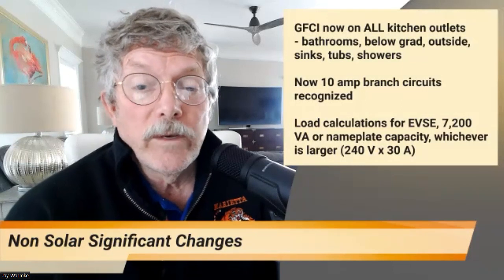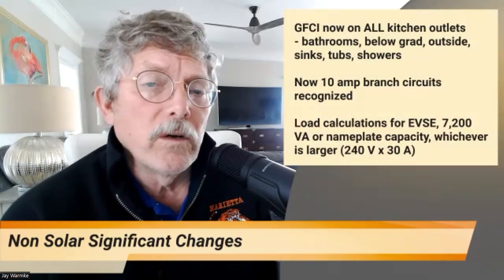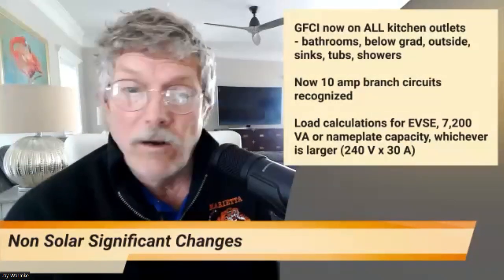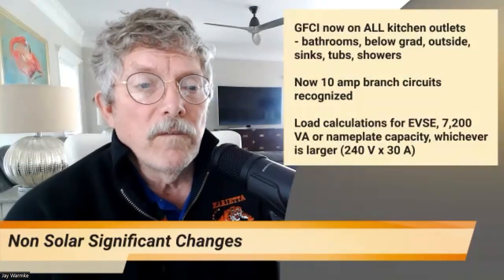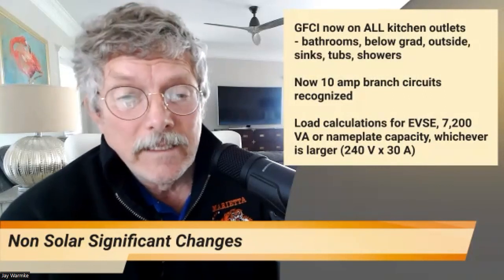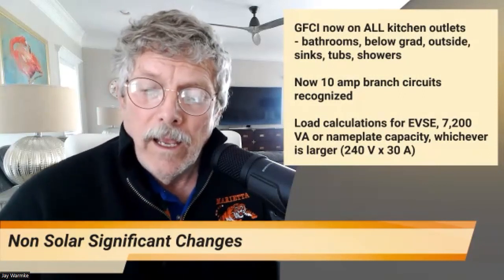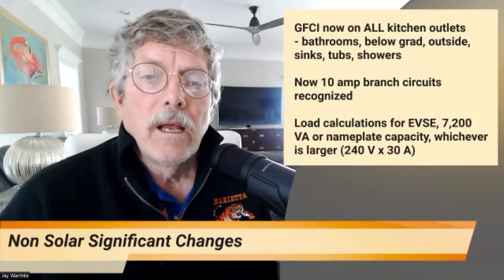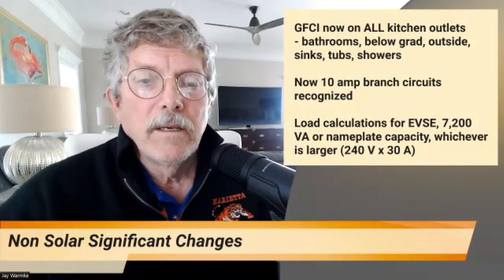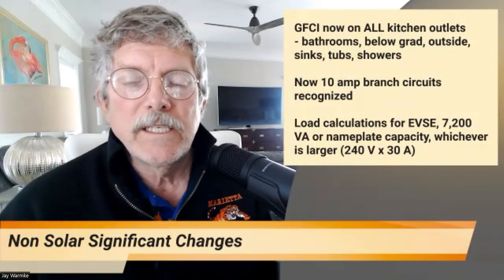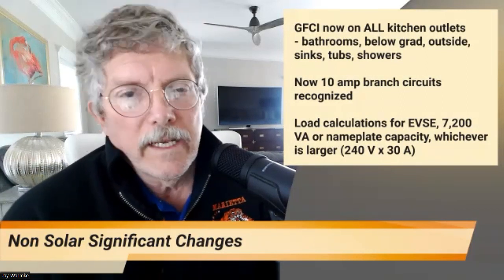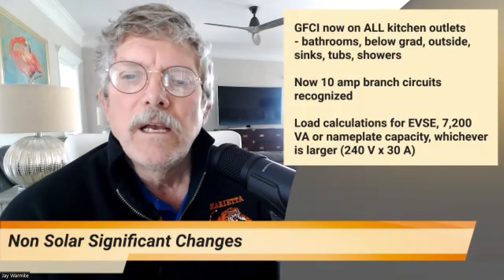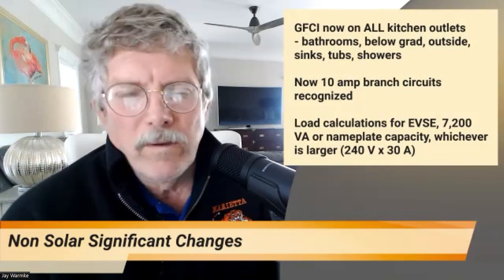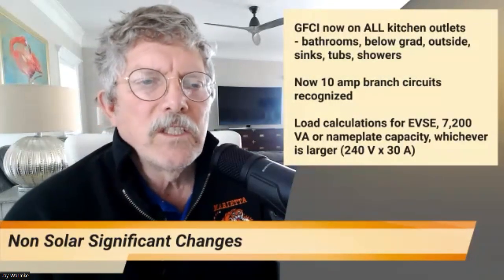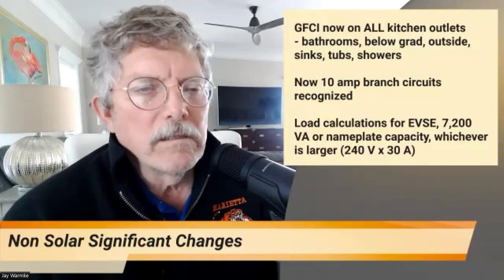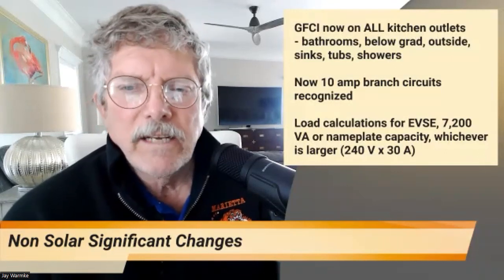Another thing in the 2023 code, I had heard the rumor that they were going to require GFCI outlets in all outlets in the home starting with the 2023. Well, they didn't require that. But what they did require is in the kitchen. Before, it was just kitchen countertop outlets that had to have GFCI outlets. Now, every single outlet in the kitchen has to have GFCI outlets. They also, of course, essentially anywhere where there's water has to have a GFCI outlet. So if there are tubs, showers, sinks, anything near that has to have GFCI.